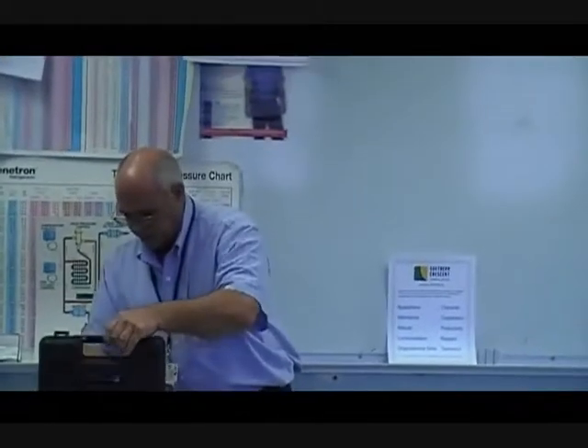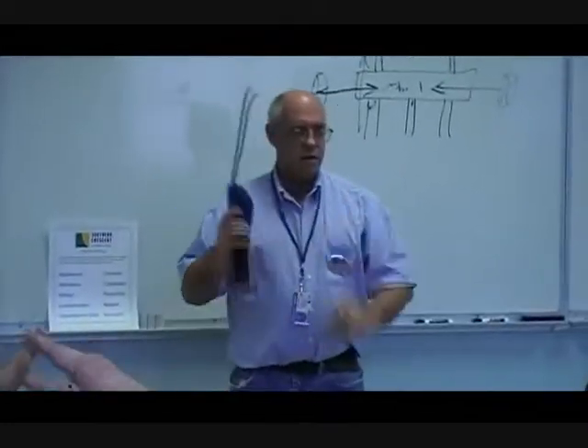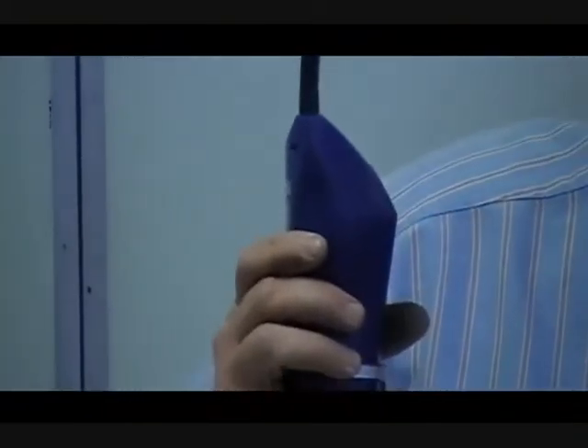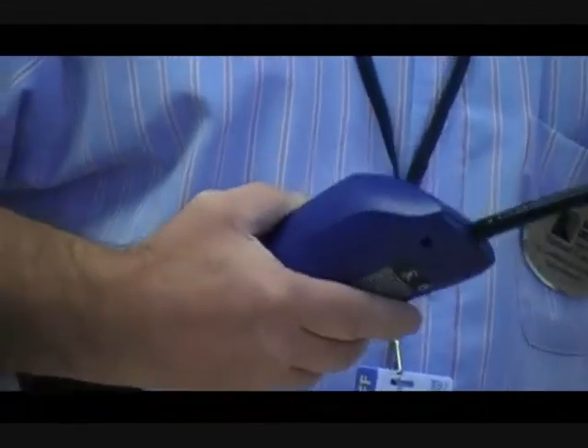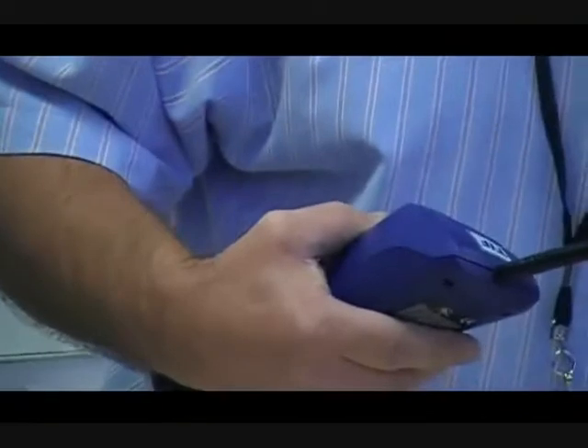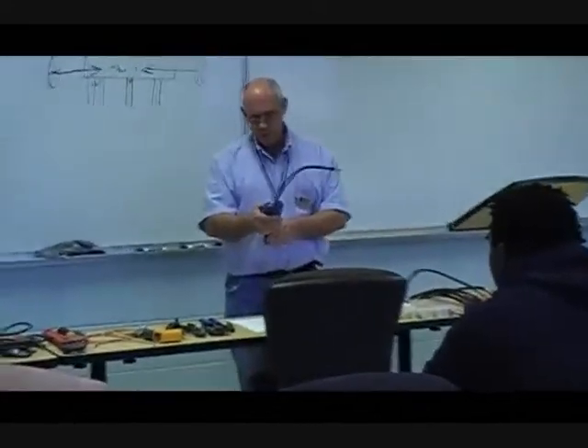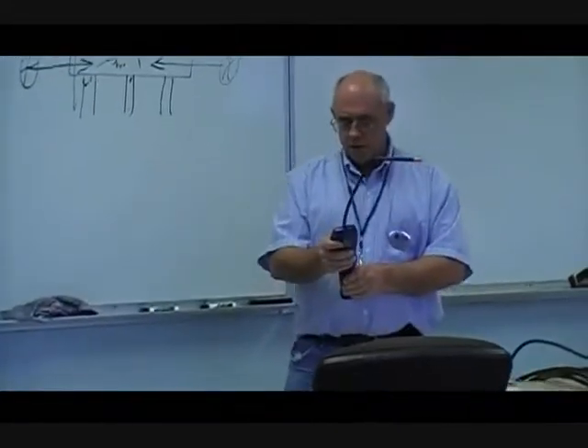This day and time, with the cost of refrigerants, we don't want them leaking out. Electronic leak detector. How sensitive is that? You should be able to pick up a rate of less than a quarter ounce a year. Sometimes you'll actually have enough residual in a hose to pick it up. You hear it pick up there? That's residual within the hose itself. Here's a problem though. What is any problem?